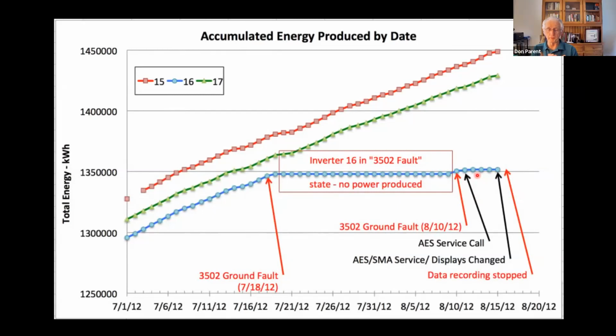This is where we lose all information. When they installed the new display, they set the date to be sometime in the future. And the minute they did that, they caused the inverter to start overwriting its history. So that's when data recording was stopped, or at least we had no access to it. But we were able to send the SD card out to a company to recover data that had just been erased. So we did get 4 days of data just prior to the date of the incident.